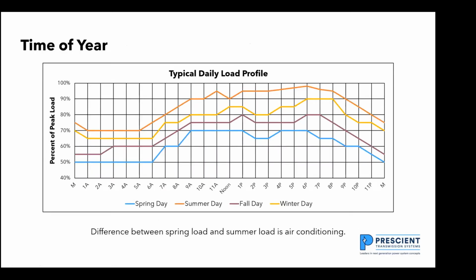Another thing that's important to recognize is the time of the year. The loads on the power system change daily, they change hourly. And what I'm trying to show on this graph is that if I look at the spring day here, the load on a spring day is about 70%. Under a peak load condition, summer loads on this circuit, the load is up to about 95%. So the difference between 95% and 70%, this is a 25% increase in load, and that's due to people turning on their air conditioners.